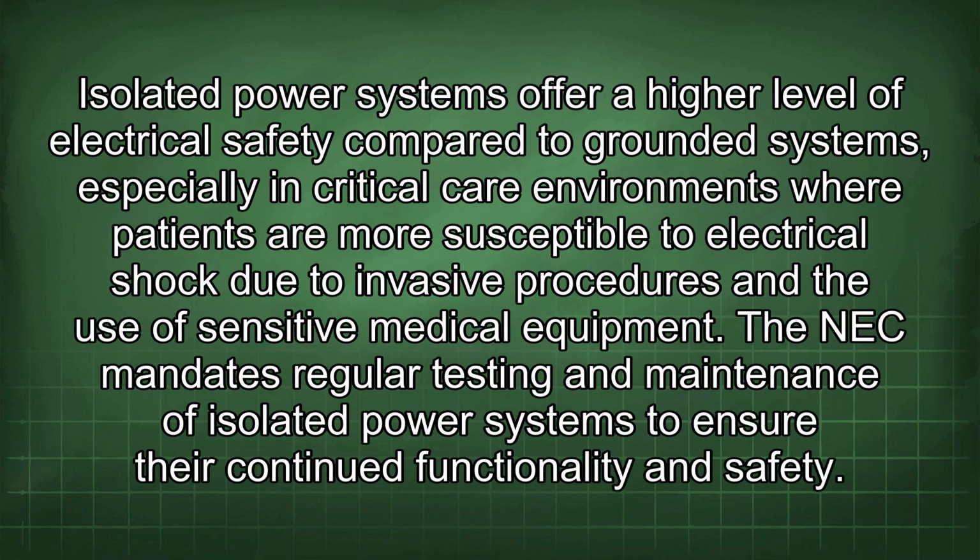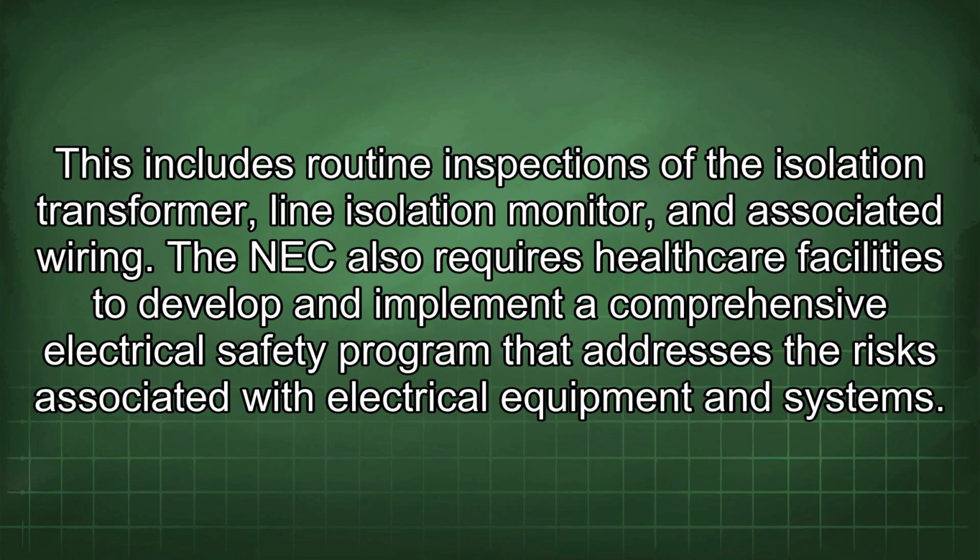Isolated power systems offer a higher level of electrical safety compared to grounded systems, especially in critical care environments where patients are more susceptible to electrical shock due to invasive procedures and the use of sensitive medical equipment. The NEC mandates regular testing and maintenance of isolated power systems to ensure their continued functionality and safety. This includes routine inspections of the isolation transformer, line isolation monitor, and associated wiring.